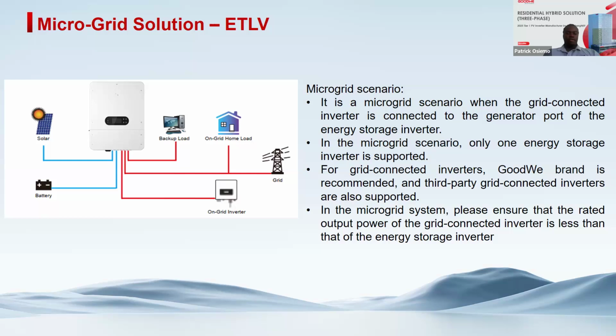If you have a grid-tied inverter, whether it's GoodWe or even another brand, you can still connect it to the same diesel generator port. Why would you do that? Because with the ETLV solution, you can achieve the microgrid scenario. So what is microgrid? Now, you do have your critical loads connected on the backup port of the ETLV. In case the grid fails, then the ETLV will still allow the on-grid inverter to continue generating and both the ETLV will be powering the critical loads which are on the backup port.